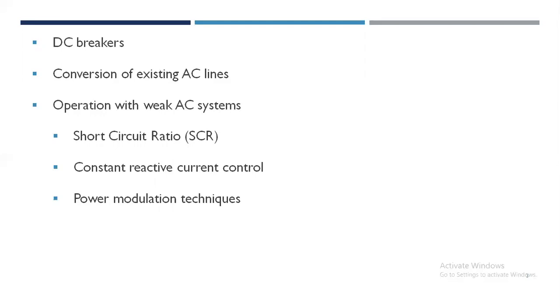An experimental project of converting a single circuit of a double circuit 220 kV line was commissioned in 1989 and 1990 in India between Lower Sileru and Barsoor under the National HVDC project. It is feasible to convert the double circuit AC line to a bipolar HVDC line with substantial power upgrading of about 3.5 times.